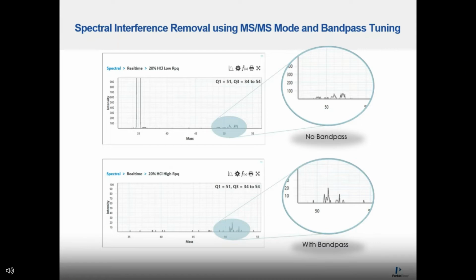Only ICP-MS with bandpass will give you a true detection of chromium and vanadium at lower levels, where having a Q1 in front of a passive cell isn't enough. So to speak, the performance of the NexION 1000 or 2000 with ammonia reaction mode in vanadium and chromium determinations at mass 51 and 52 is much more superior than an ICP-MS triple quad system with a passive cell.